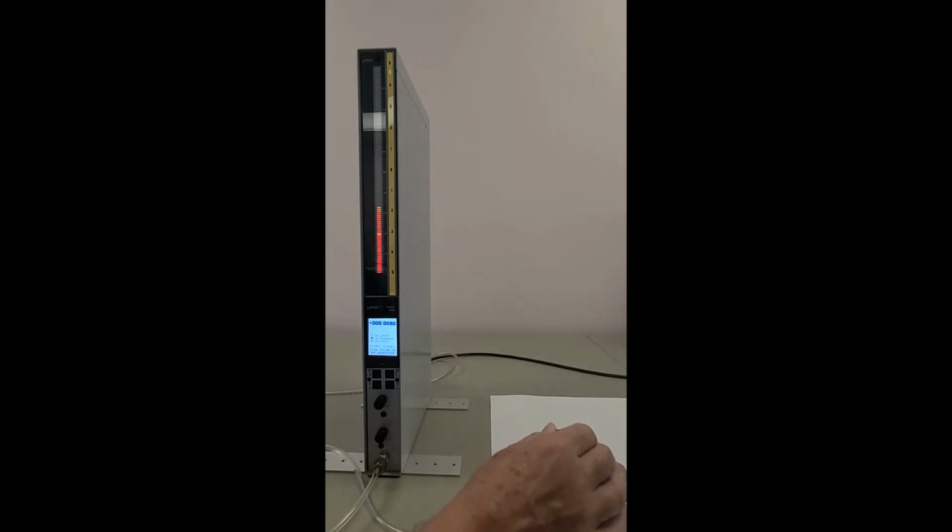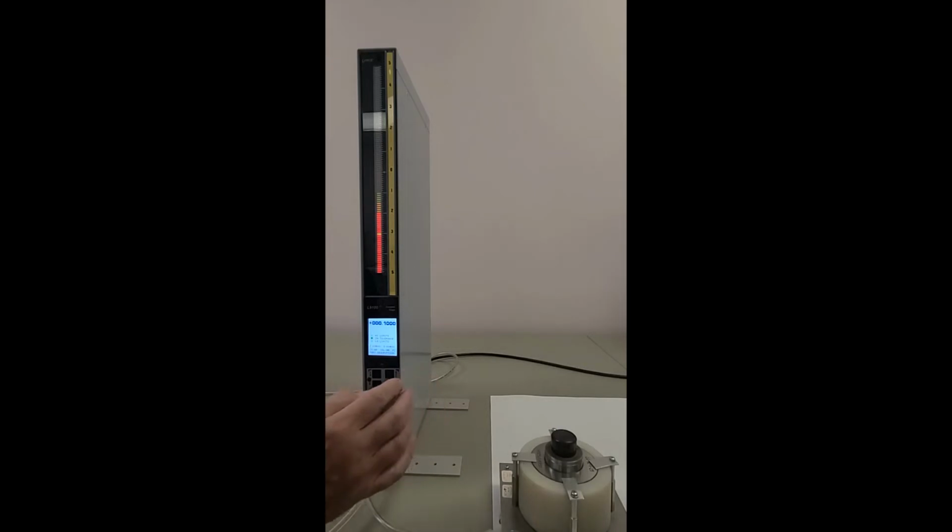So as I turn here, okay, I've gone through a revolution, and there's the difference it's seen between the max and the minimum positions, and I can press a reset and it will put it back to the 20% point. When we're using the max minus min TIR function, the zero set point will always start 20 LEDs up from the bottom. That allows for a more full usage of the total display.